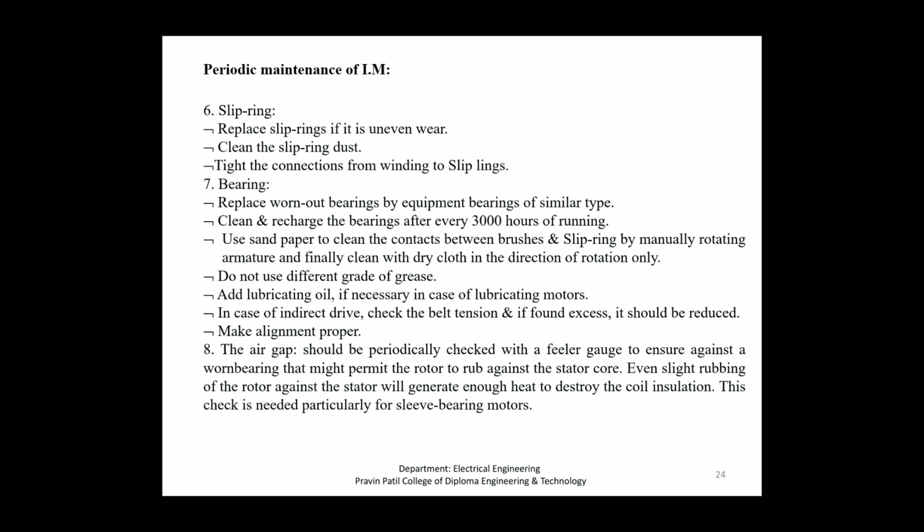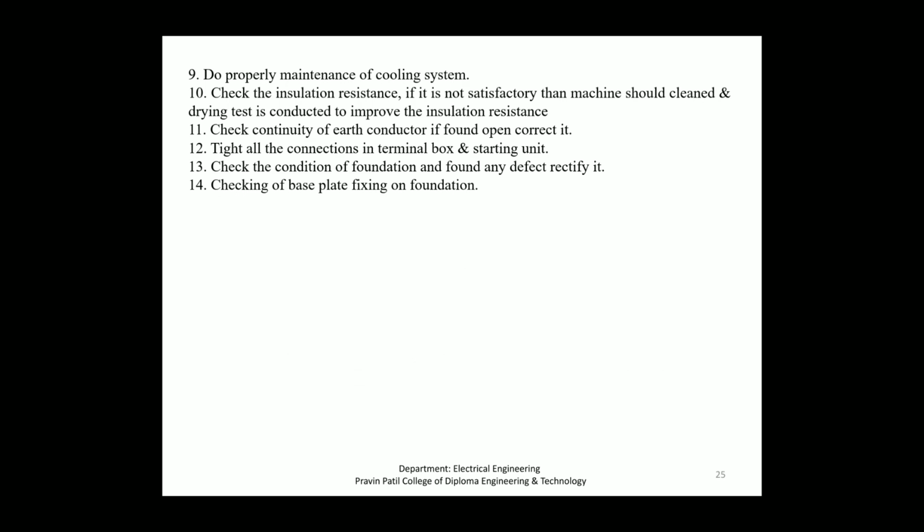Next one, do proper maintenance of the cooling system. Check the insulation resistance. If it is not satisfactory, then the machine should be cleaned and a drying test conducted to improve the insulation resistance. Check continuity of the conductor. If found open, correct it.